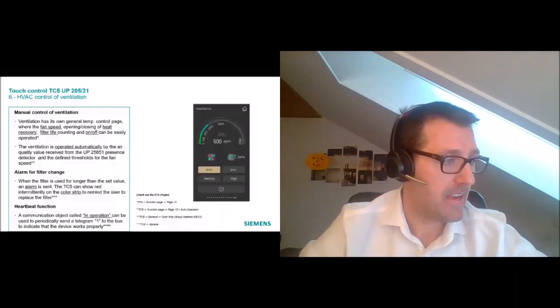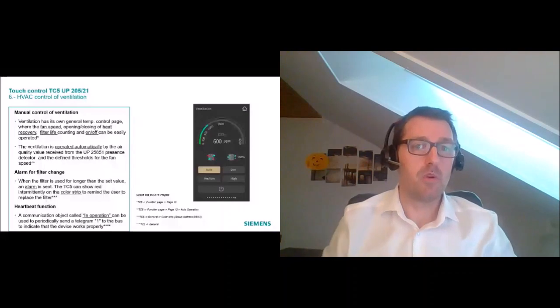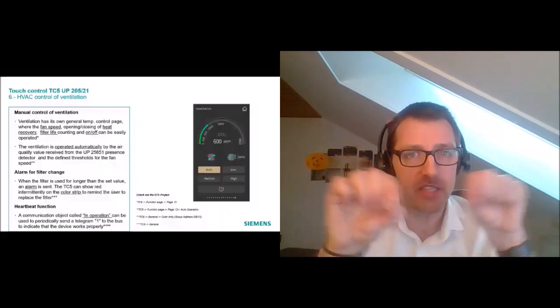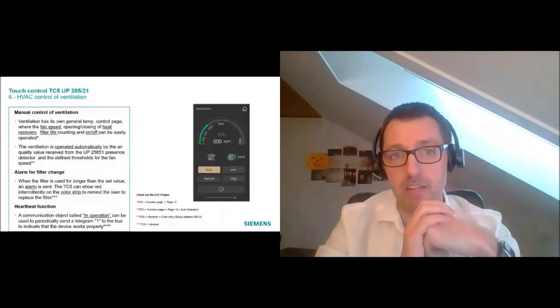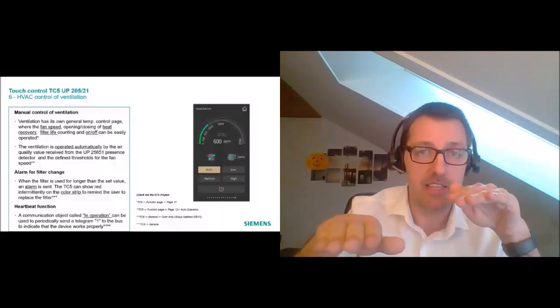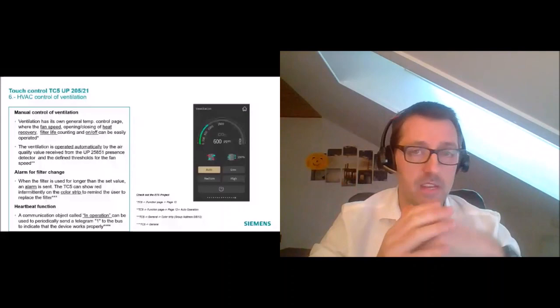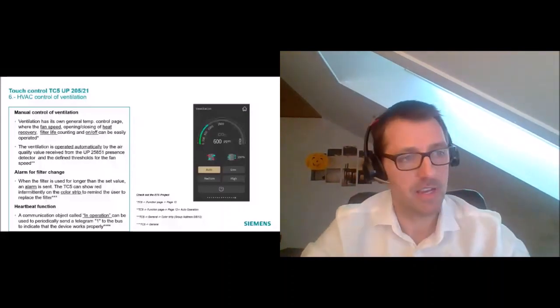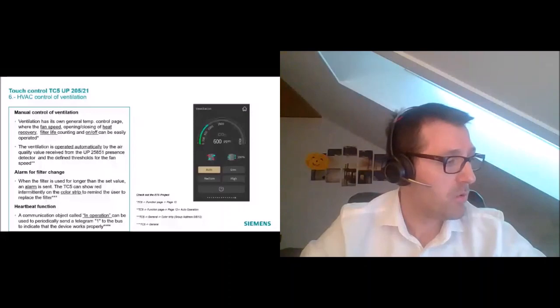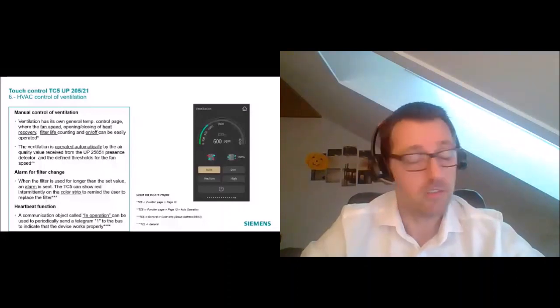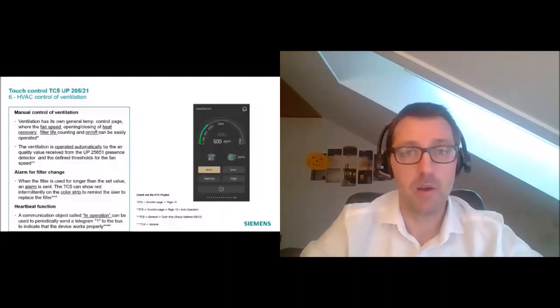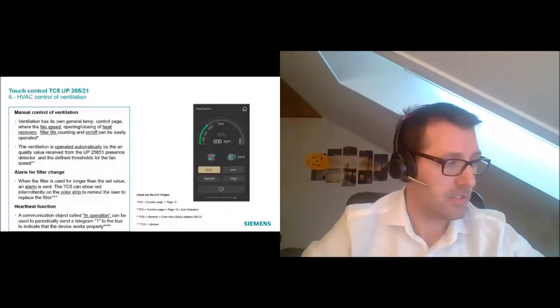For the filter alarm, we can use the color LED strip on the TC5. We configure it so that when the filter needs to be changed, the LED flashes red — a visual indication that something requires attention. For the heartbeat function, we have a communication object that periodically sends a telegram to the bus confirming the device is active.